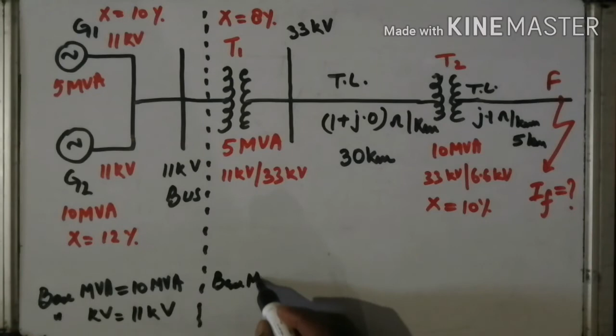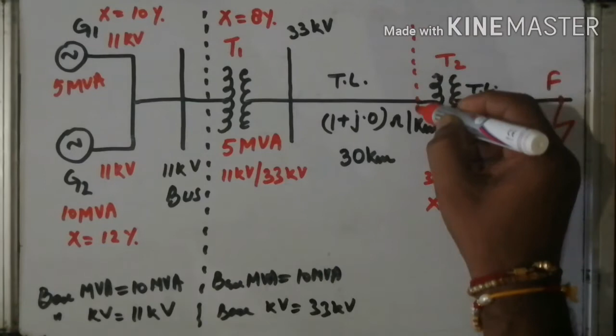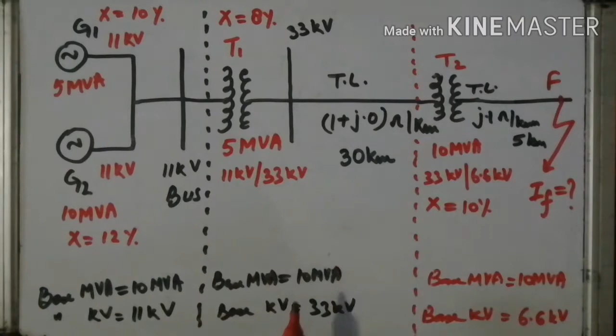Okay, here the base value, that is base MVA, is 10 MVA and the base kV is 33 kV. After that, now at this point, the base value is same throughout the circuit, but the base kV depends upon the voltage ratio of the transformer, that is 6.6 kilovolt. This one T1 is the step up transformer. It converts 11 kV into 33 kV, after the transmission by the TL transmission line. This one is the step down transformer having the voltage ratio 33 kV to 6.6 kV. Okay, these are the base MVA rating, which is same, that is 10 MVA, and base kV is 11 kV, 33 kV and 6.6 kV.